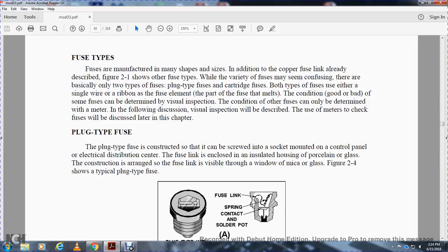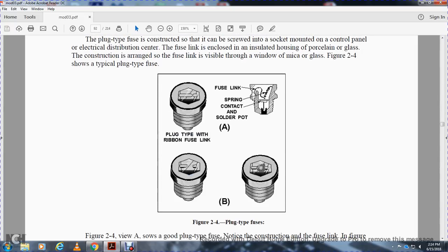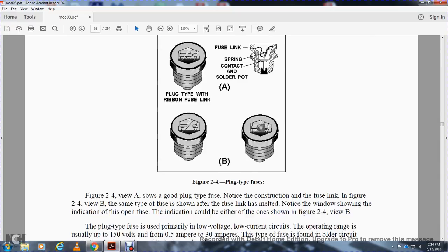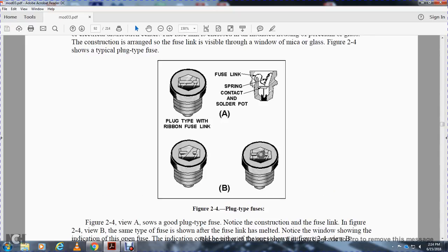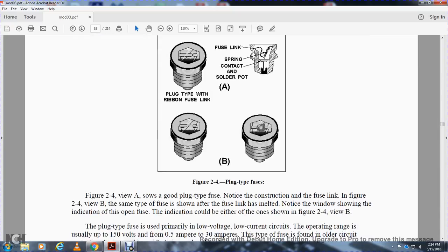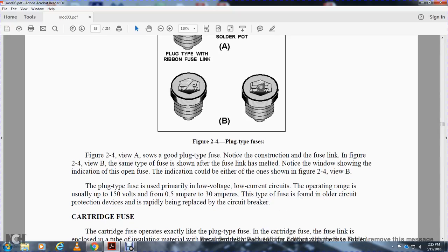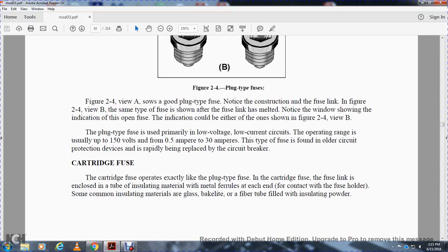Figure 2-4 shows a typical plug fuse - the plug type fuse with ribbon fuse link, spring contact, and solder pot. Figure 2-4, View A shows a good plug type fuse and notes the construction of the fuse link. In Figure 2-4, View B, the same type of fuse is shown after the fuse link has melted. Notice the window showing the open fuse indicator. The plug type fuse is used in low-voltage, low-current circuits, with an operating range of usually 150 volts and from half an ampere to 30 amperes. This type of fuse is found in older circuit protection devices and is rapidly being replaced by circuit breakers.